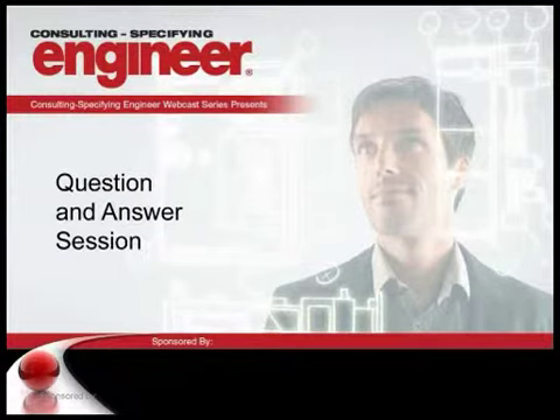but I think you should go to your authority having jurisdiction, because you would be forced to specify equipment that has a much higher rating when the probability of an occurrence of a fault during that overlapped time period is probably really, really small. So I think it's a question that you need to ask your local code authorities when you start designing the systems. Yeah, and I would agree with Dean. It would be somewhat related and separate when you're talking about overlapping neutrals versus the syncing of the phases when you do a make versus break. So it would actually be two separate. One you might make for 5 seconds or some short amount of time. In other situations, just the neutral.